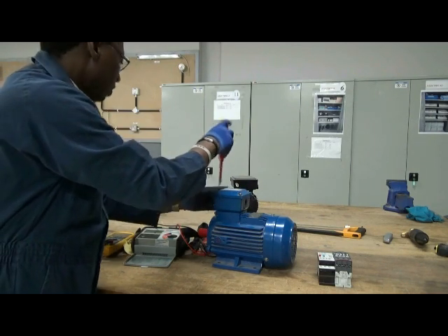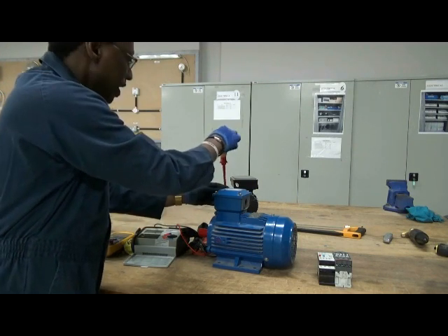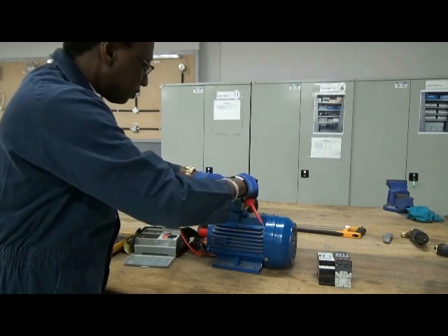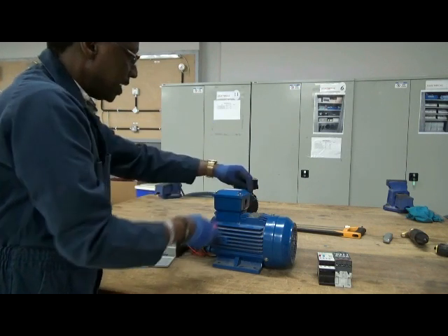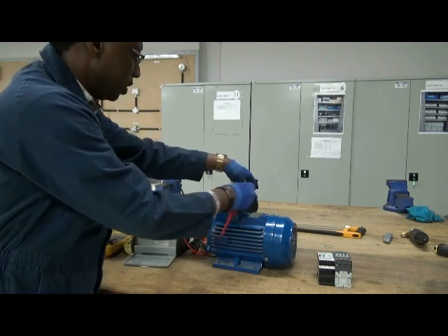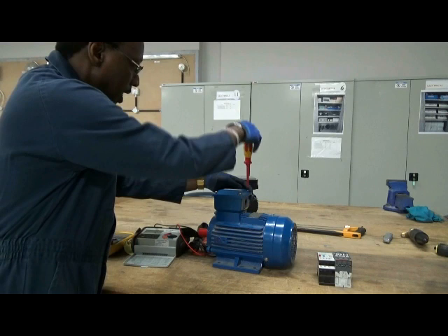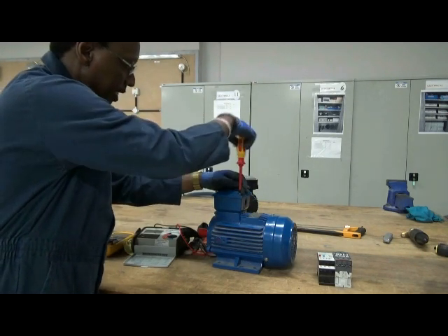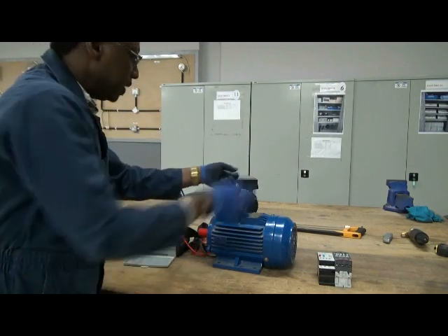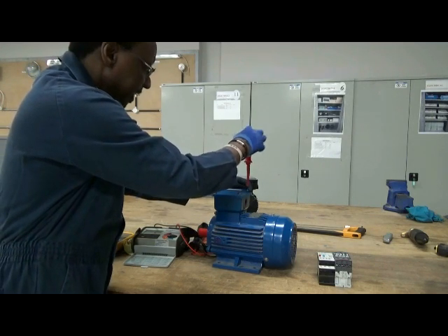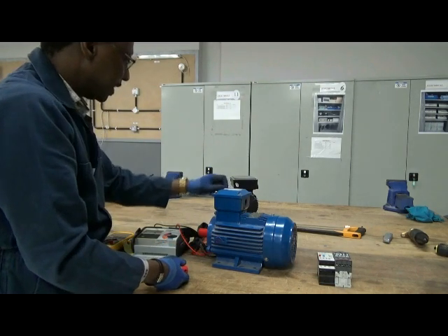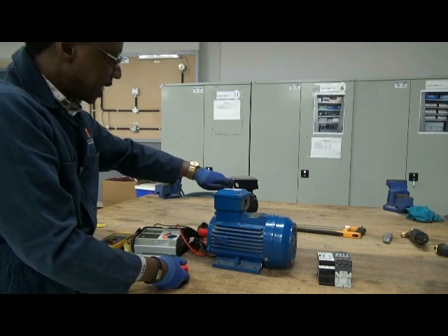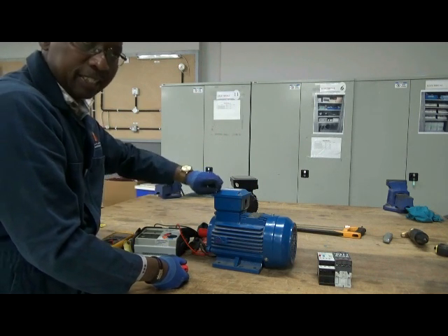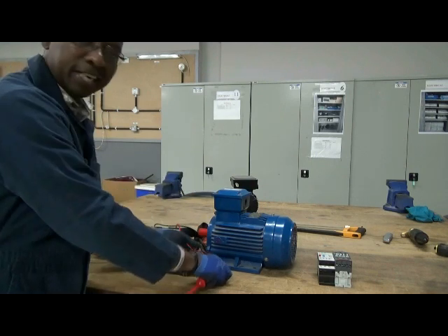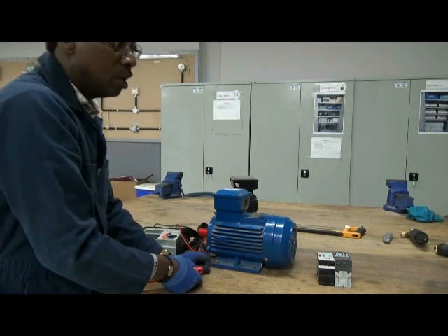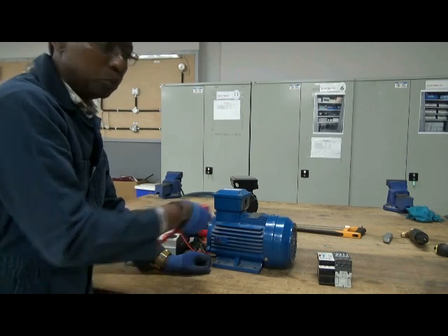The three-phase motor is made up of three windings that are separated from each other by 120 electrical degrees. So what happens is when you connect your three-phase supply, that's the red, yellow, blue lines, you notice that a magnetic field is going to be produced around the stator, and it will start rotating at what we call a synchronous speed. That's the speed of the rotating magnetic field in the stator. Now, because the rotor has also some rotor windings, this rotating magnetic field will be cutting the rotor windings, thereby inducing an EMF, according to Faraday's laws, which says that whenever a magnetic field cuts a conductor, an electromotive force is induced in that conductor.